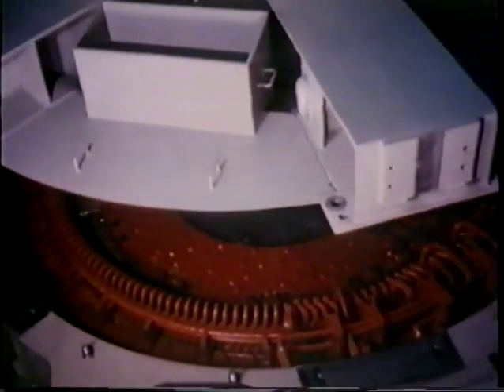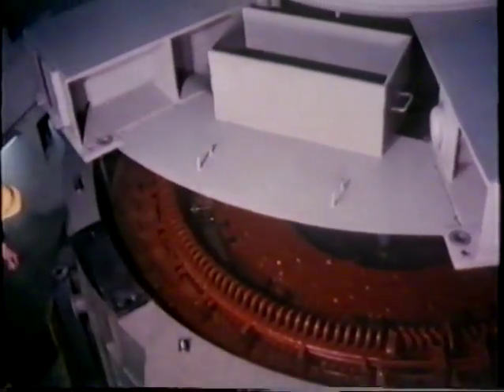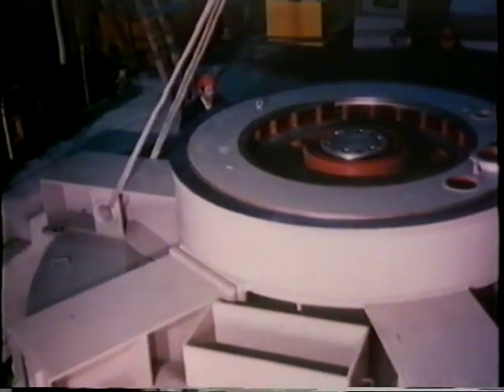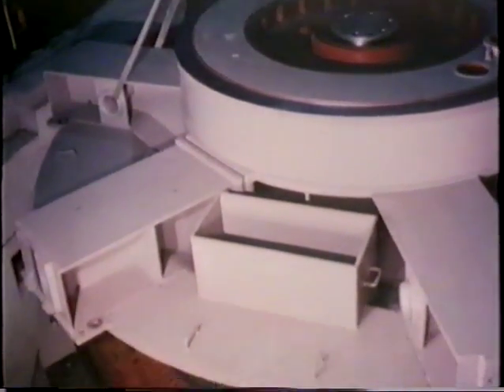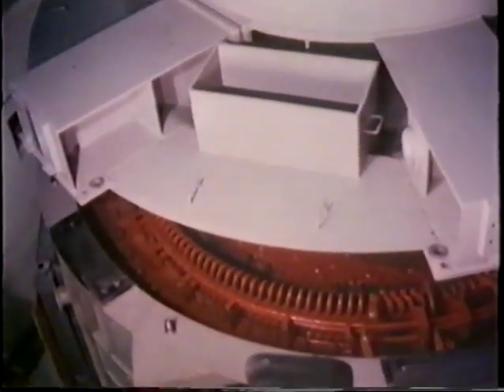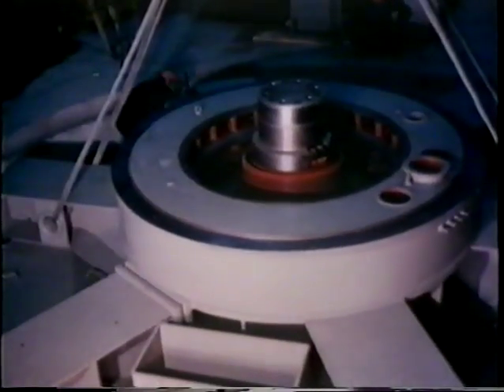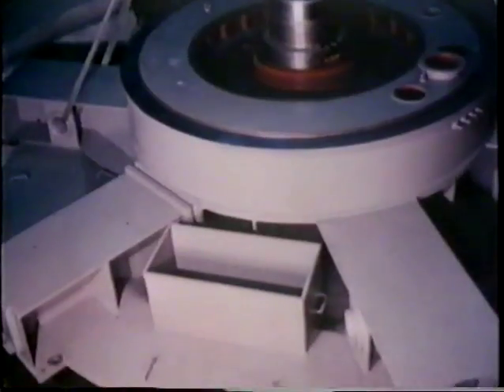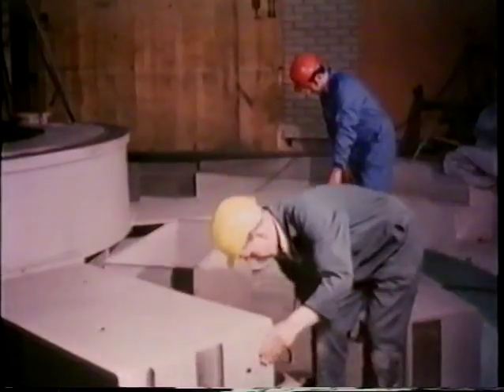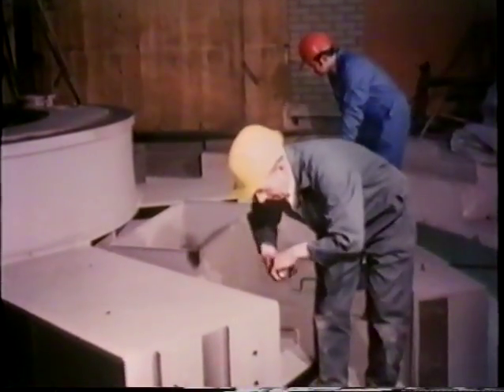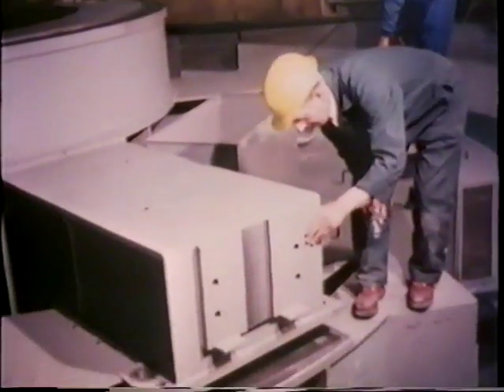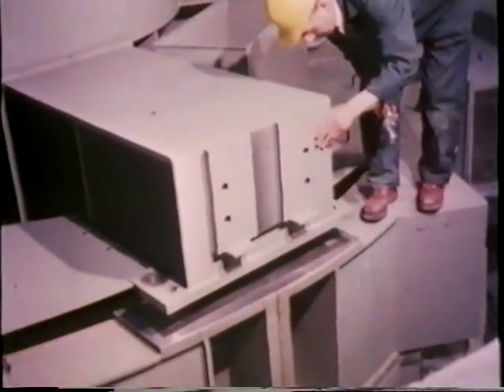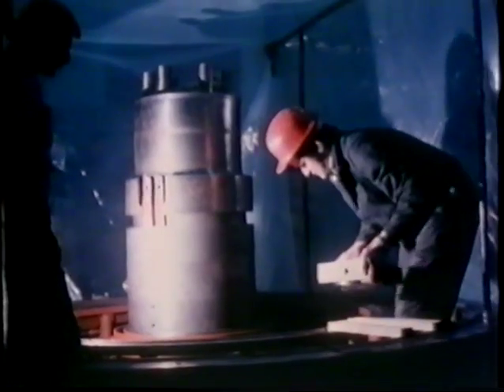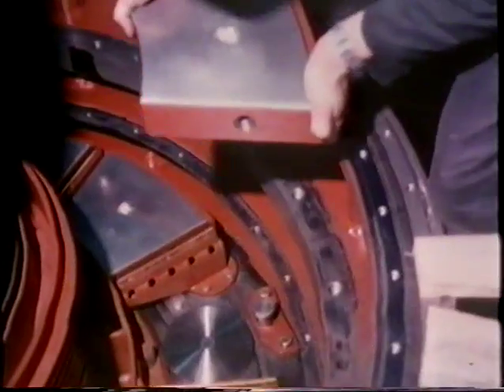Class F insulation with epoxy resin impregnation is used for the stator insulation, and therefore carbon dioxide fire protection is omitted. Standstill heating is provided to avoid condensation when the unit is off load. The thrust bearing is of critical importance.